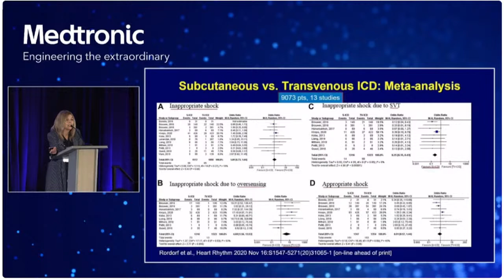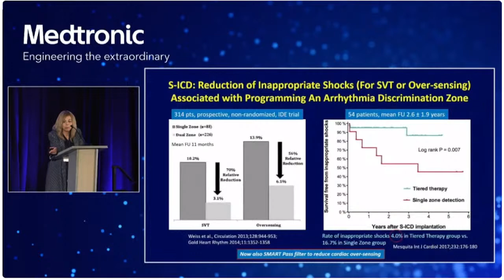And this shows that if you program on that conditional zone, you don't totally get rid of it, but you can reduce inappropriate therapy for SVT as well as oversensing by a significant degree. There's also another thing they have now, a smart pass filter, that should be programmed on now out of box in their devices, but that should always be programmed on to help reduce this cardiac oversensing.